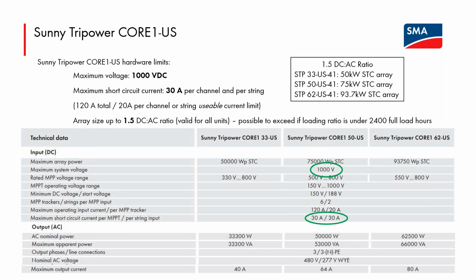So I had alluded to this earlier. Each tracking channel can be driven fully through a single positive and negative input pair for the inverter's body. So potentially if you're using a high current module, bifacial module, you expect a lot of backside gain, having one string of modules come into each tracking channel might be the correct design choice. Or if you have an array that is far removed from the inverter location, having 2 strings using a Y-branch connector to combine the 2 positives and 2 negatives at the array into a single positive and negative, and bringing that back to each tracking channel might save on conductor costs. So that ability to drive each tracking channel fully through a single positive and negative input has been used by a lot of customers to good effect.